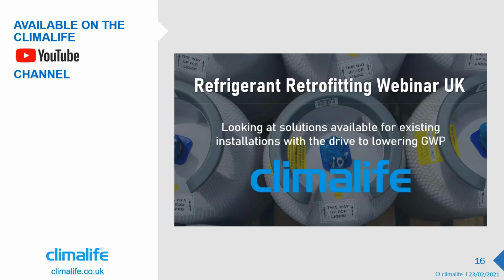I don't intend going through all the options for each refrigerant. After all, we did a webinar for that last year, and it is available on our YouTube channel. Just search there for Climalife refrigerant retrofitting and you'll find it. In that webinar, I discuss options for many different refrigerants, including all those with a GWP above 2,500, such as 404A and 507. I will cover these today, along with 407A and 407F, and also R134A.